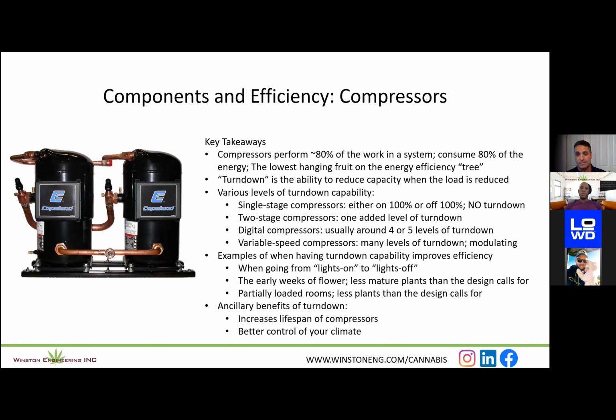If you have too much capacity for the load, you're going to be burning energy and you're going to lose control. If you don't have enough capacity for the load, you're just never going to turn the equipment off and you're going to keep running it, right? So it's really a matter of dialing that in and getting the right design up front. Examples of where this comes into play: lights on to lights off. Once you shed those lights, you're effectively killing about 50% of the load in the space. If you don't have the ability to turn down your refrigeration, your cooling, or your heat rejection, you're going to overcool and overdrive the space, and have trouble maintaining the conditions you want.